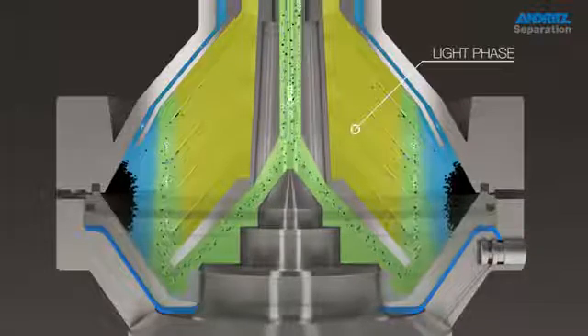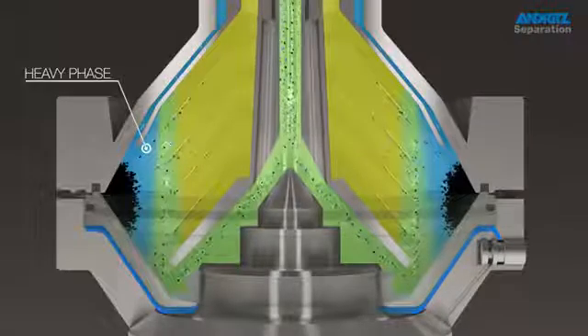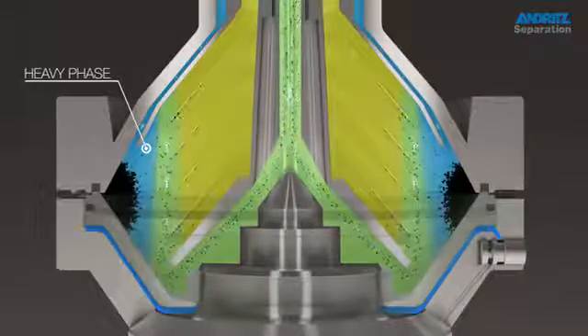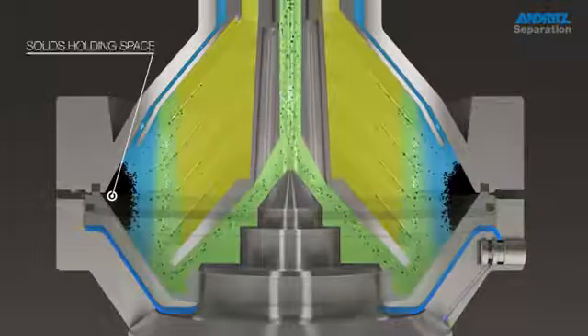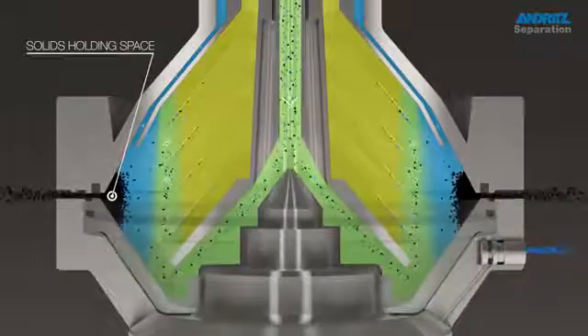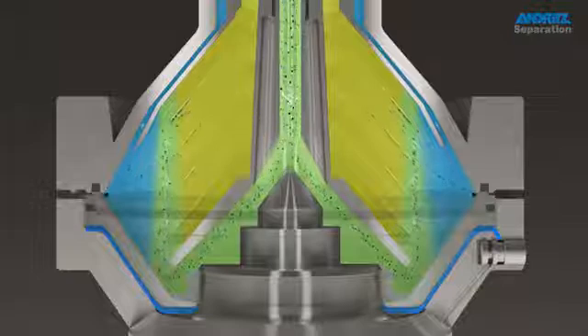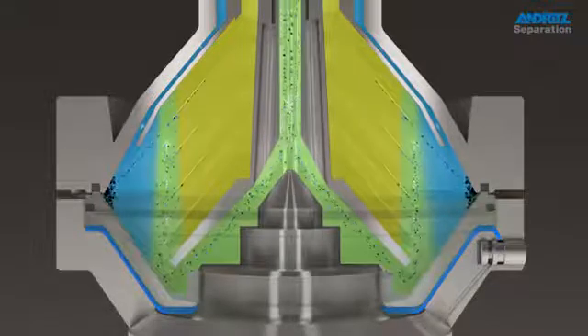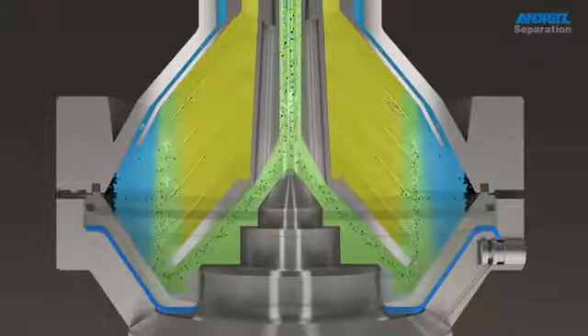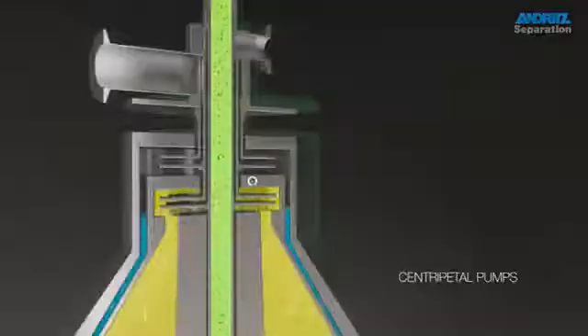The light phase is concentrated in the inner part of the bowl, while the heavy phase is forced towards the outer part. Solid particles are forced towards the outer part of the bowl, accumulating in the solids holding space, and are discharged automatically in very precise shots at regular preset intervals.